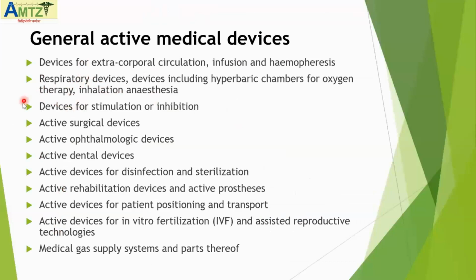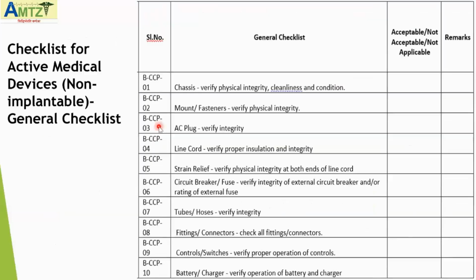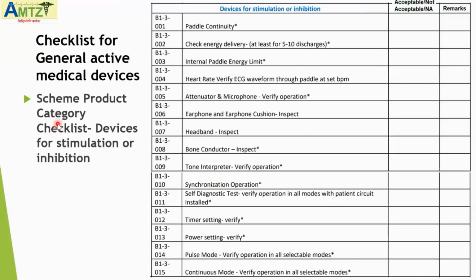Again, I'll take one example, that is device for stimulation or inhibition. I have already shown the general checklist. Now we will see the checklist for the scheme product category, device for stimulation or inhibition. You can see that the first point is paddle continuity, especially for the defibrillator machine. Then check the energy delivery for at least 5 to 10 discharges, again for the defibrillator machine. Under this, 15 points are covered.